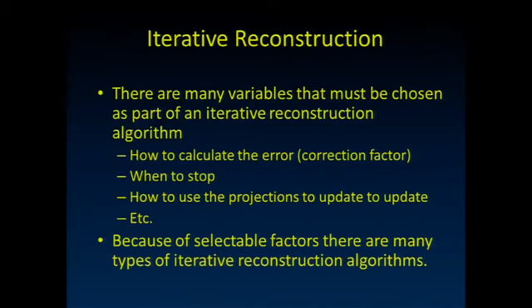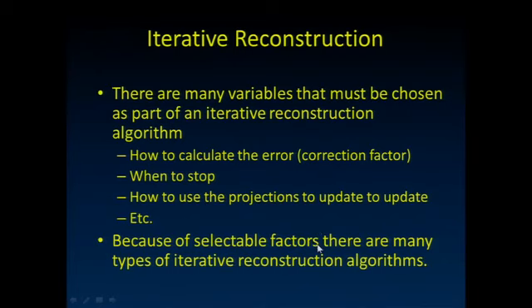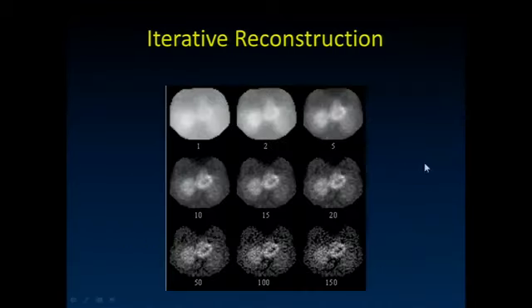Unfortunately there are many variables that must be chosen in iterative reconstruction: how to calculate the correction factor, when to stop, how many iterations, how to use projections to update the data. Because of that, there are a lot of iterative reconstruction algorithms out there. Every manufacturer's filtered back projection algorithm basically does the same thing; you can use slightly different filters but the algorithm is the same. The iteratives are much more variable and harder to generalize.